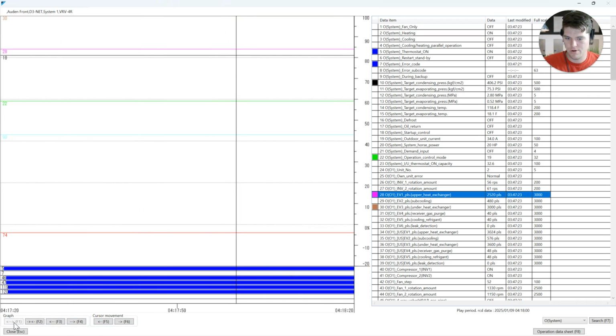Okay, here you go. Here is the data you sent me for 10 minutes, right? Man, yeah, this really paints the picture for me. That's why when we record data, guys, as technicians, I want more. We need more, right? You see how quickly I got there? And this has just been 40 minutes, and I just showed you and peeled back the onion for checking four-way valves, for checking discharge superheat, for checking suction superheat, for checking subcooling, that the liquid line just turned into a low pressure line.